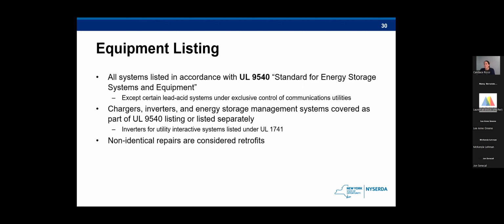And next we have the equipment listing requirement. So to further safeguard against hazards, systems must also be listed in accordance with UL 9540, the standard for energy storage systems and equipment. So chargers, inverters, and energy storage management systems, if not covered as part of that UL 9540 listing, must be listed separately. And this is basically just giving all those different listings that are required for parts of the system.